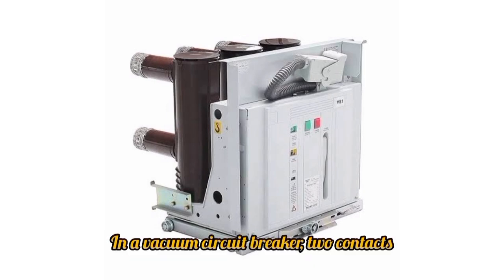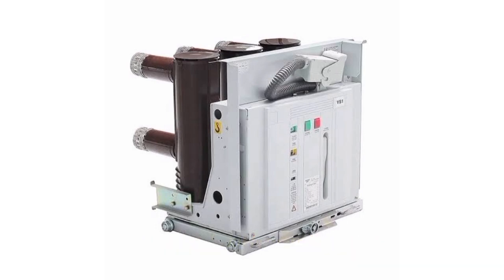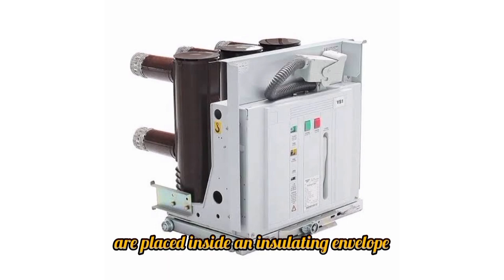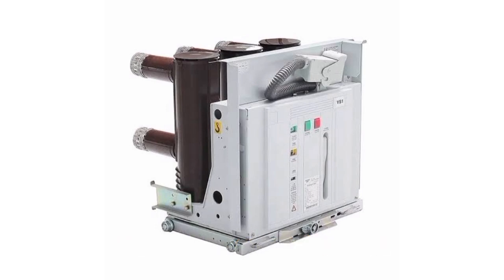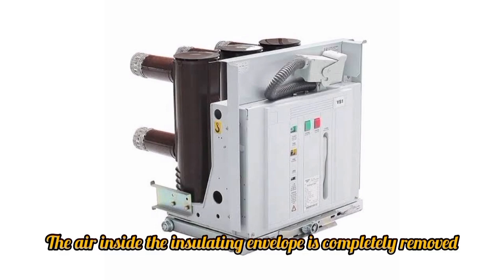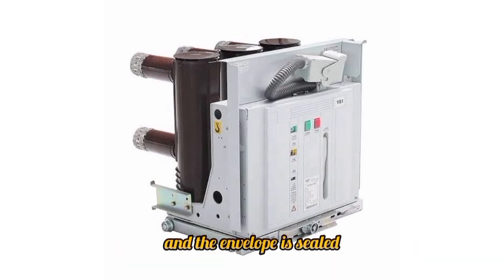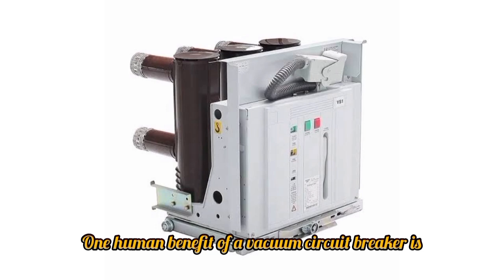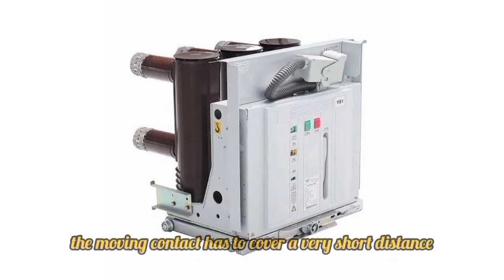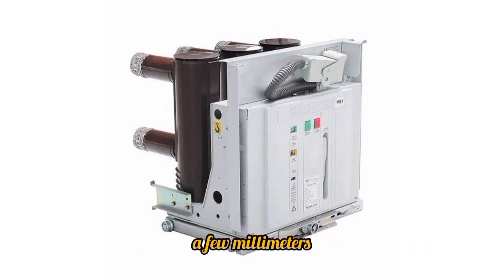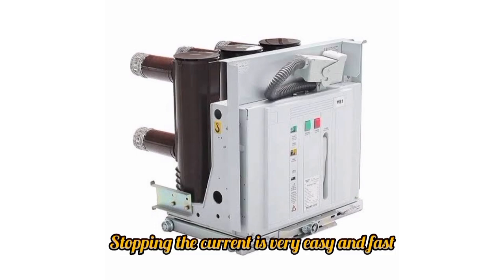In a vacuum circuit breaker, two contacts, a fixed one and a moving one, are placed inside an insulating envelope. The air inside the insulating envelope is completely removed, and the envelope is sealed. One main benefit of a vacuum circuit breaker is that during separation, the moving contact has to cover a very short distance, a few millimeters. Stopping the current is very easy and fast.